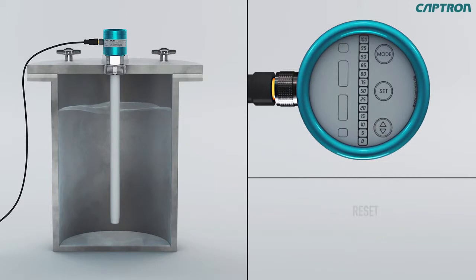Now we will go through the reset function. This should be done before the first alignment, but also always do a reset before using a new medium. Touch mode and up-down at the same time for approximately 5 seconds until the display 0%, 100%, as well as MIN light up. The now blinking value is the last minimal set value. Let go of the buttons at the same time.